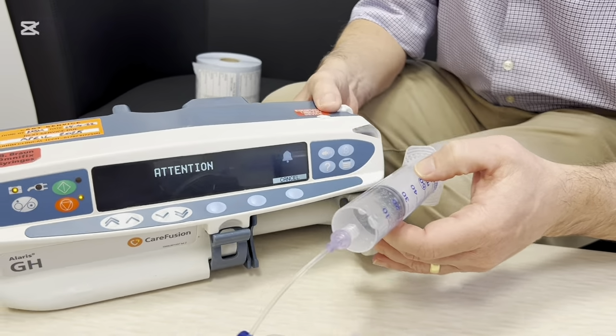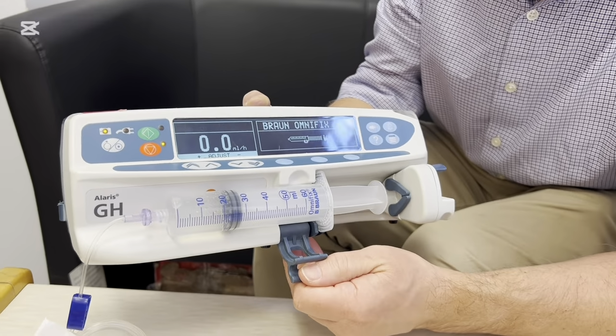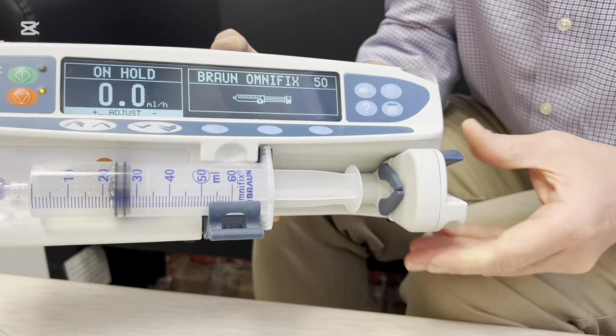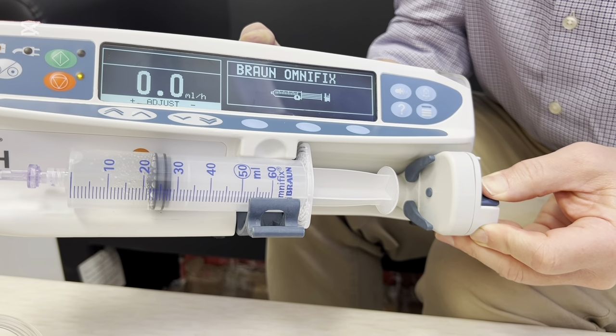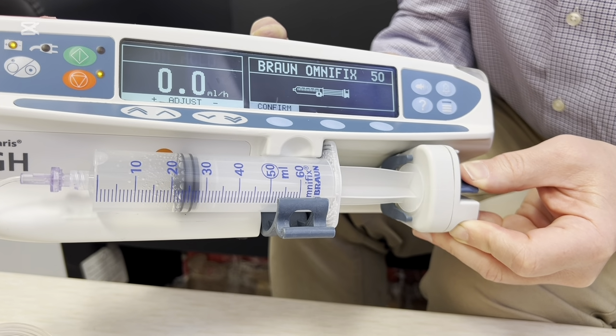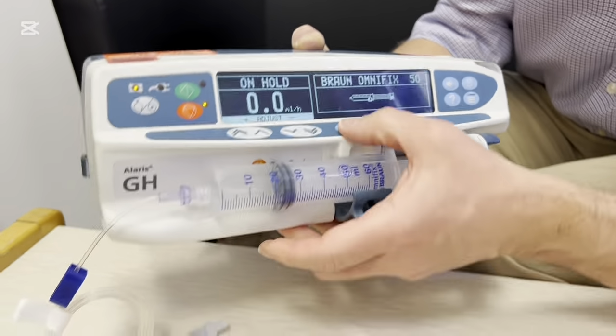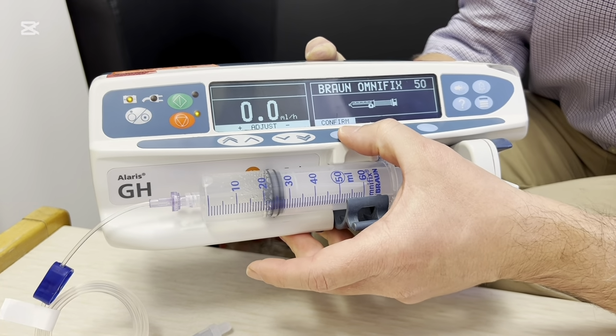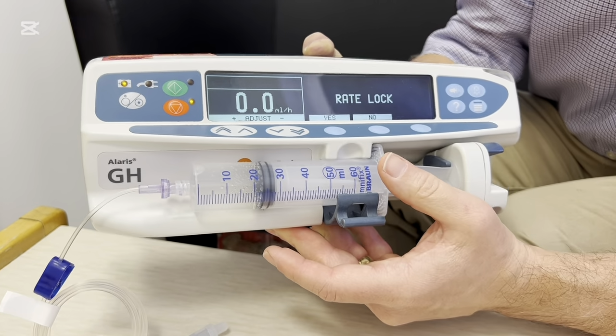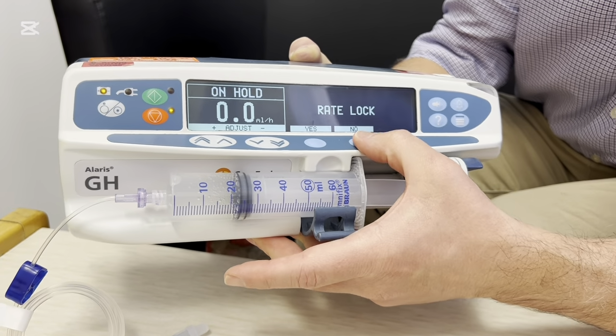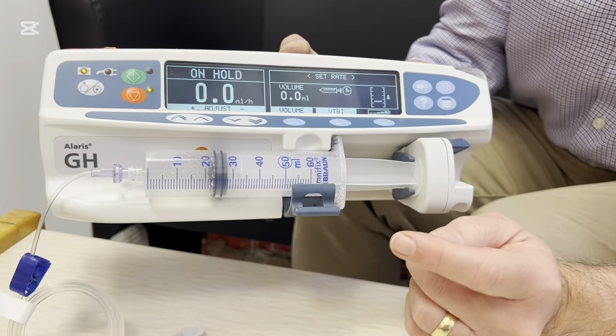Next, load the syringe into the infusion pump. So open the clamp into the syringe holder, close the syringe clamp, take the plunger, disengage it from the gears, slide it onto the end of the syringe, and before you connect it to the patient, it's just asking us to confirm that it's a Braun Omnifix syringe, which it is. Rate lock, no. We'll show you how to cancel the rate lock later.